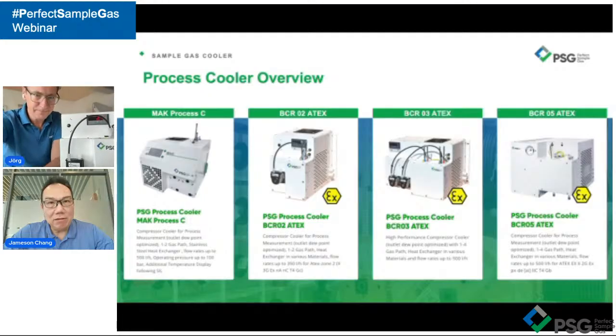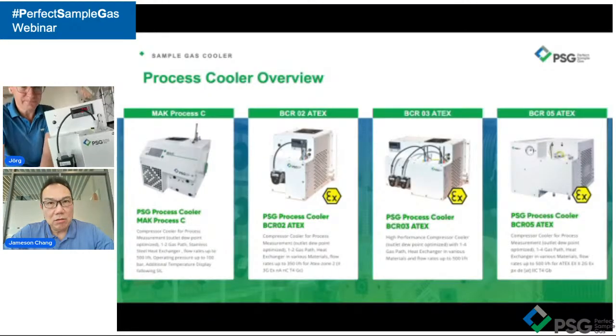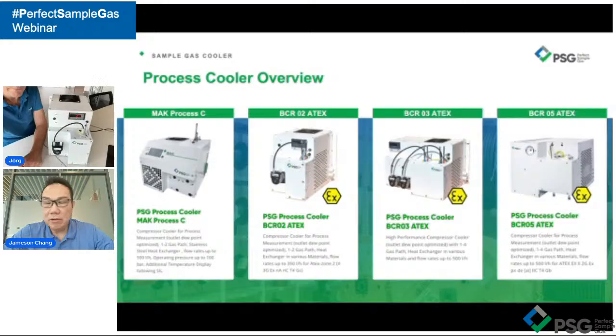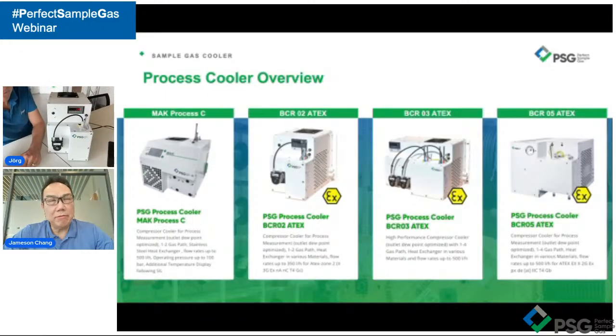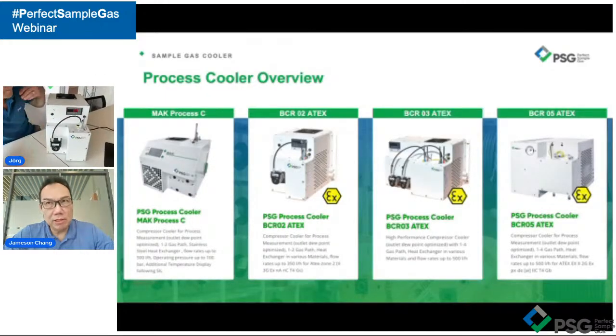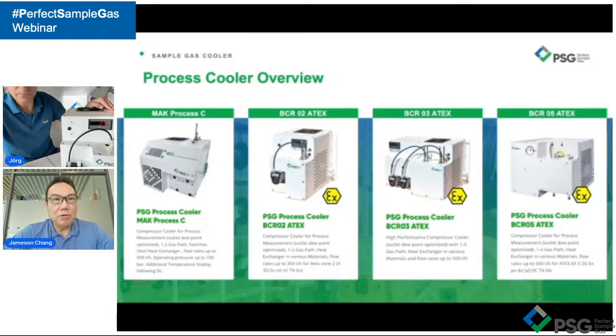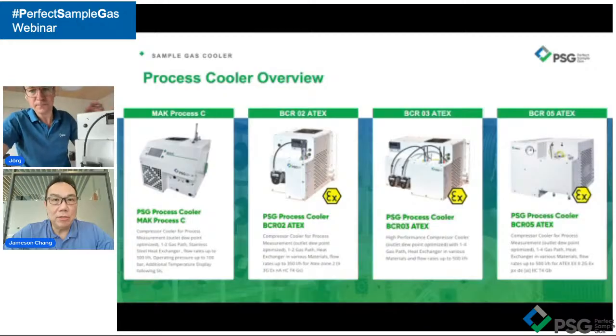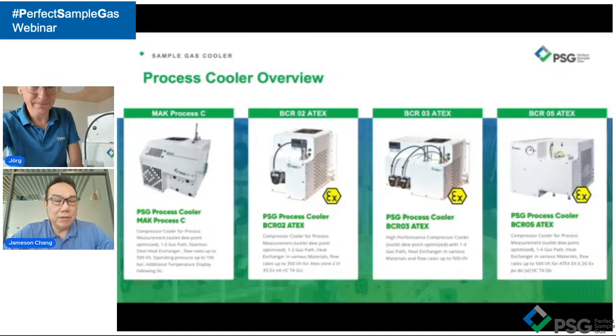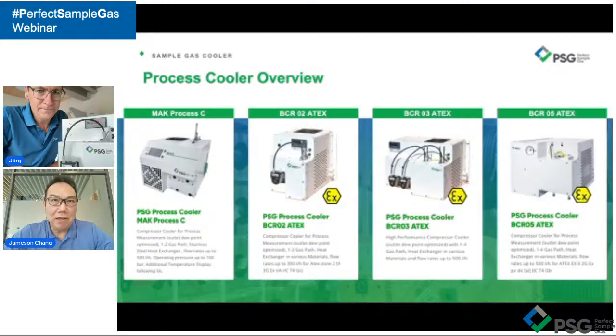The BCR is able to take positive pressure. Many times the MAK family are for emission monitoring. They need a sample pump, and the sample is measured at negative pressure. But the process is clean, and the process is normally positive. For that reason, depending on how positive the pressure is, you can either use a peristaltic pump or you can use an auto drainer, which is part of our supply.